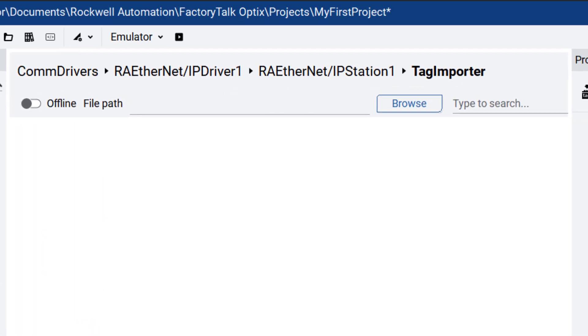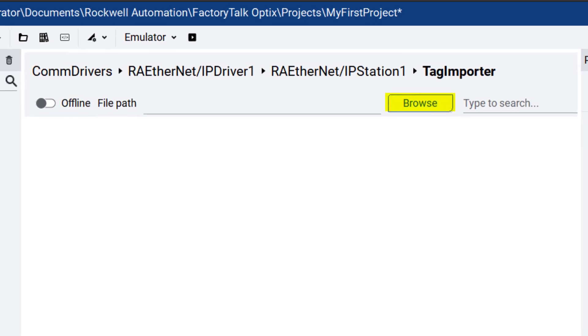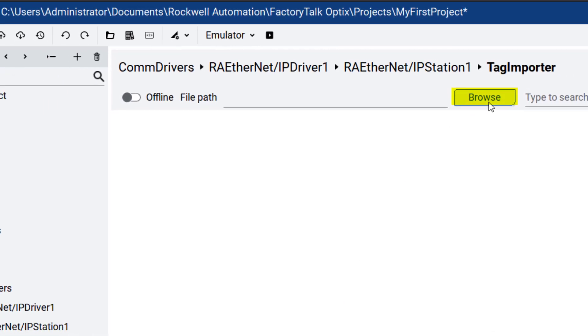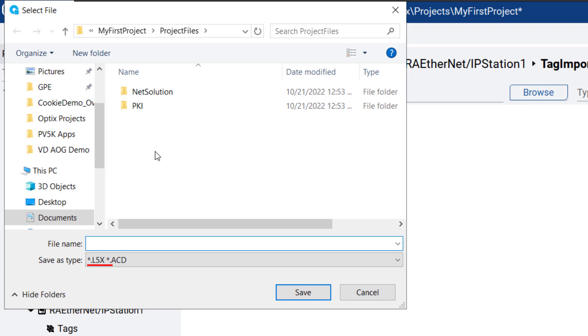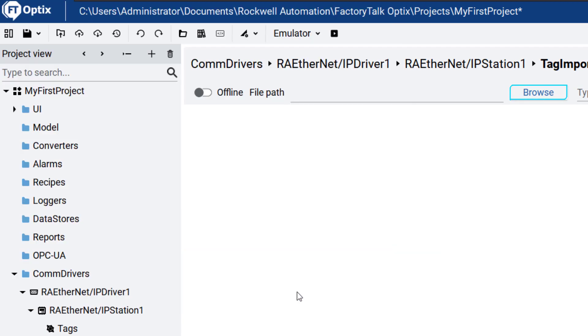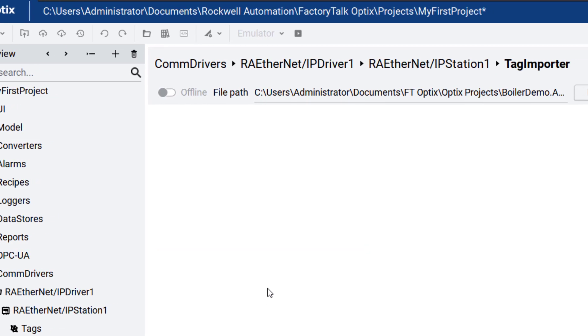In the Central Tag Importer window, the import mode can be selected as either Online or Offline. Let's do the offline import. Click Browse to select the Logix Designer Project ACD or L5X file via the Windows File Explorer. Select Save to save the file path.